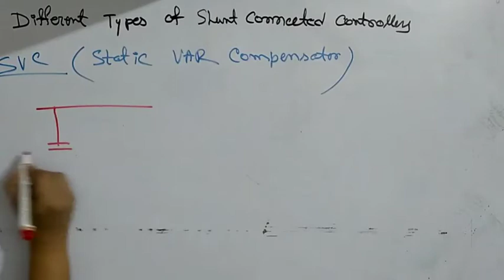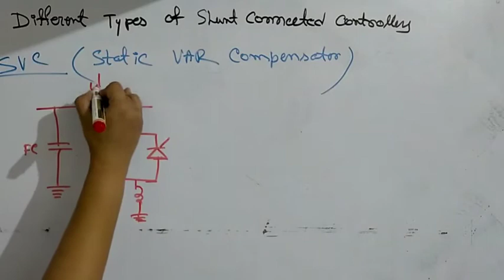Now, SVC is based on thyristors without gate turn-off capability. It includes a thyristor controlled reactor, TCR, in parallel with a fixed capacitor in its commonest form, and is known as FC-TCR type SVC. Now first I draw the schematic diagram of static var compensator. This is the fixed capacitor. This figure represents the schematic diagram of SVC, and you can see that the TCR is parallel with the fixed capacitor. This is the commonest form and it is known as FC-TCR type SVC.